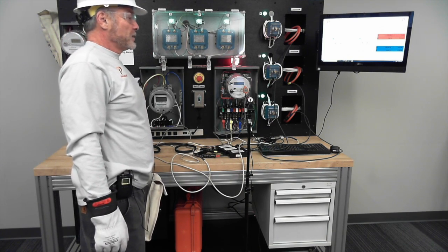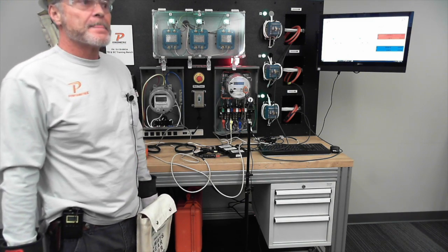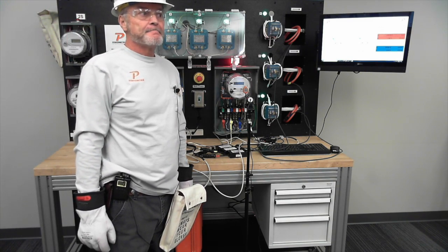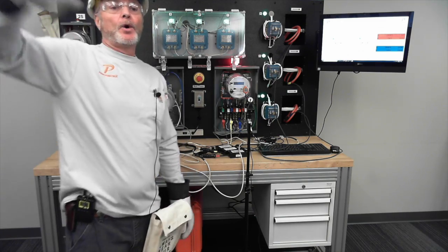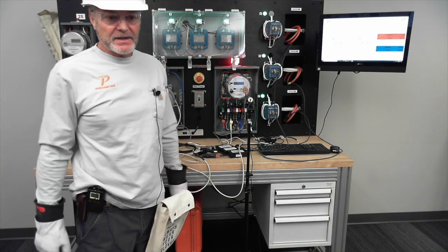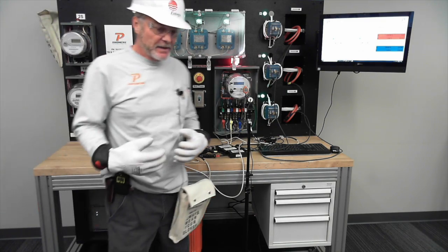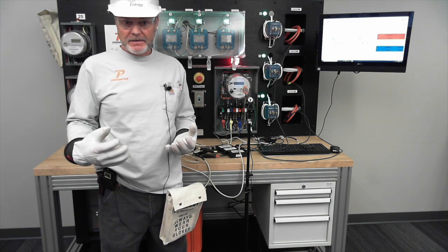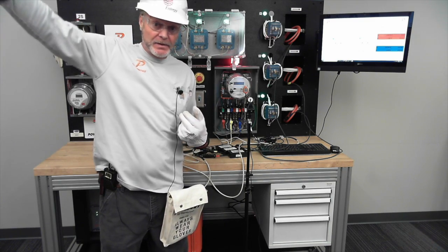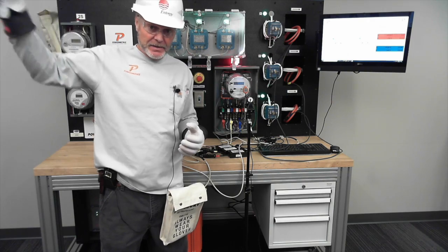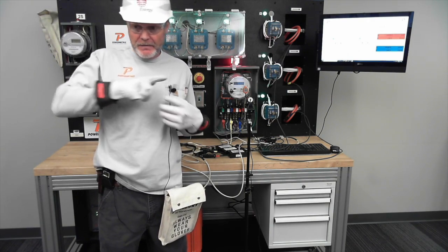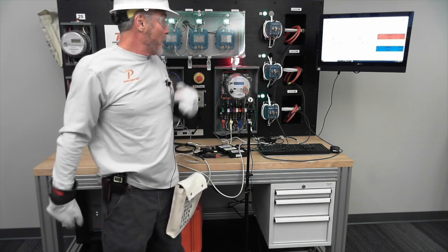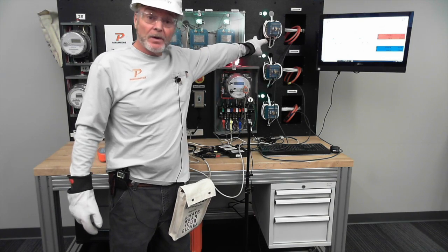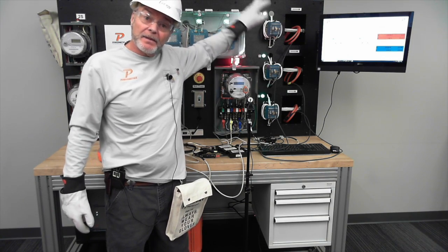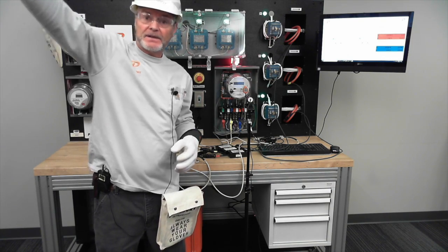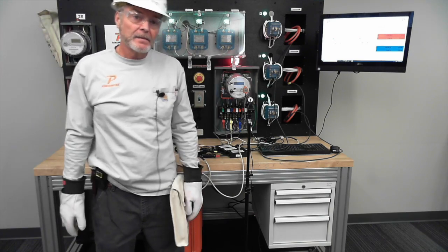If there is a secondary drop from the meter to the CT, you won't be able to see that because you're right at the CT now. That's true. I've cut out that whole length that we always concern ourselves with when we talk about putting too much burden on a CT. We talk about it could be too long a length of too small a wire, or it could be a connection or something like that. So you won't get the measure of all that long length out there, but you can do a ratio on that CT and feel pretty good about it, unless you would have a skinned wire or something between here and there. Right.